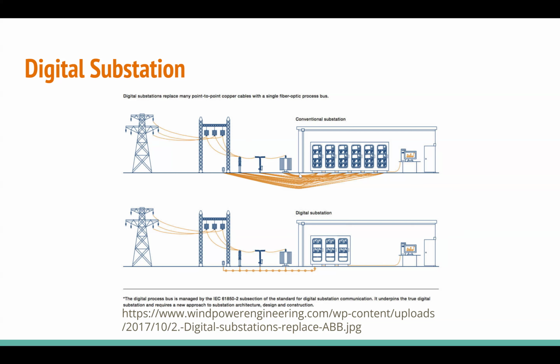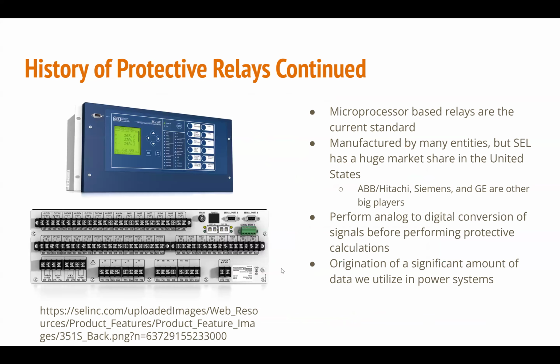With new digital substations, our goal is for all of that to be digitized. Going back to the microprocessor-based relay slide, the idea with a fully digital substation is you have methods of eliminating each of these connection types: binary outputs, binary inputs just below the fiber optic connections, and analog inputs for voltage and current.